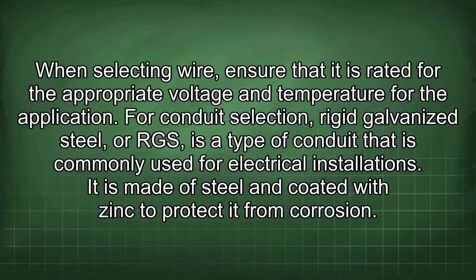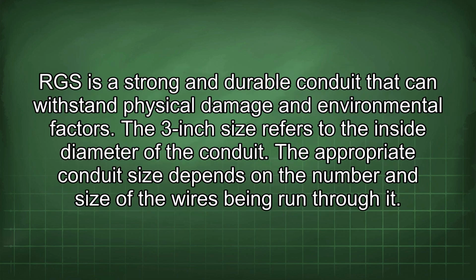For conduit selection, rigid galvanized steel, or RGS, is a type of conduit that is commonly used for electrical installations. It is made of steel and coated with zinc to protect it from corrosion. RGS is a strong and durable conduit that can withstand physical damage and environmental factors. The 3-inch size refers to the inside diameter of the conduit. The appropriate conduit size depends on the number and size of the wires being run through it.